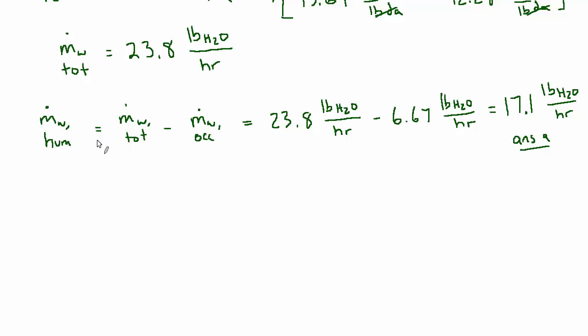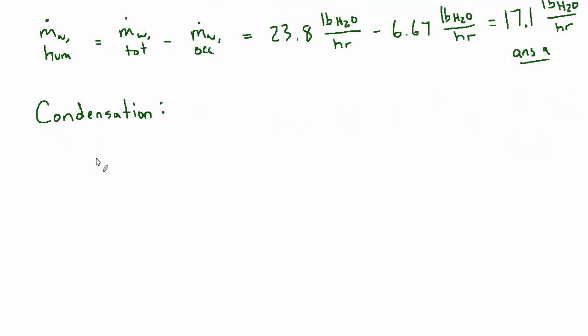And then in the second part they wanted us to determine if any condensation will form on the inside of the glass. So let's consider that - that's really going to depend on the dew point, right? So you have these inside conditions and some outside conditions. Inside we know it's 75 degrees with a relative humidity of 40%, and we can look up the dew point on the psychrometric chart by going straight to the left.